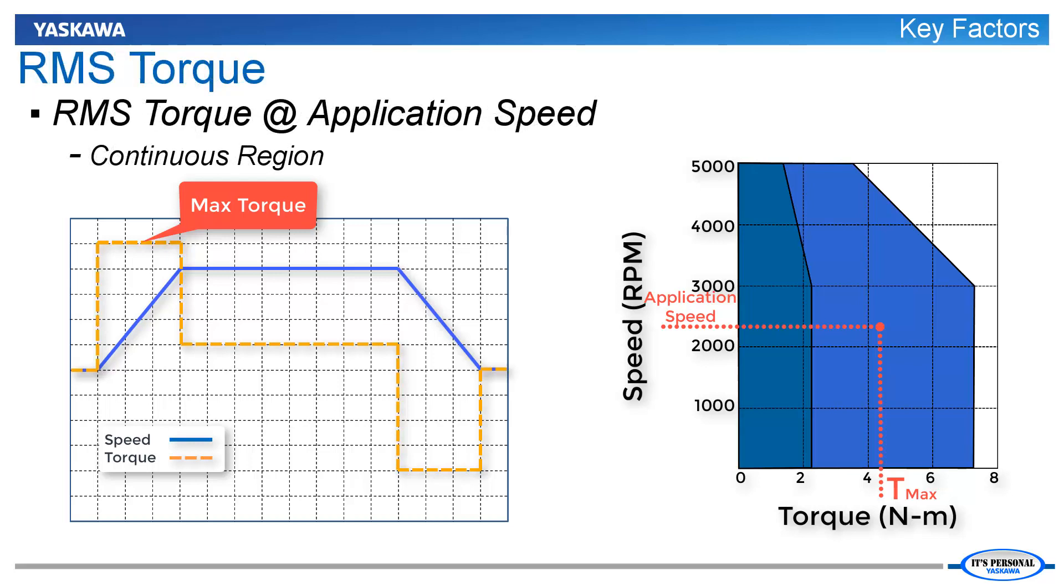Another torque calculation is critical for sizing, the RMS torque. RMS torque is a time-weighted average of the torque during a complete machine cycle and represents an equivalent steady-state torque level. For example, a servomotor with 1.2 Nm RMS torque will experience the same heat rise if it produces 1.2 Nm constant torque.